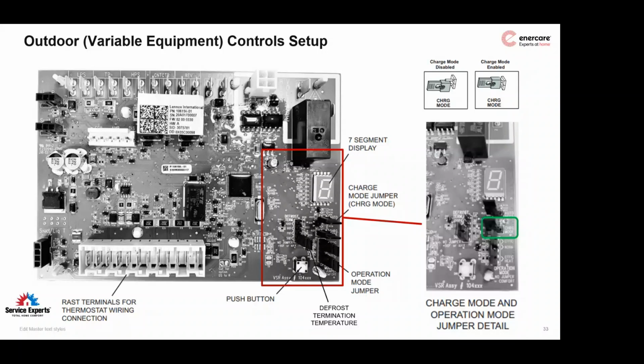Here's the caveat in a 24-volt system, however. Before you jump this charge mode pin, you need to get the indoor fan to the Y2 cooling speed, which is high speed, whatever it's been set up for the appropriate total external static pressure and CFM value you're looking for. So there needs to be a call at Y and there needs to be a call at O specifically for Lennox. They may need to be jumpered in order to get them to function. And then you can push this charge mode pin on and it will take your outdoor variable compressor to 100% and allow you to charge more quickly.